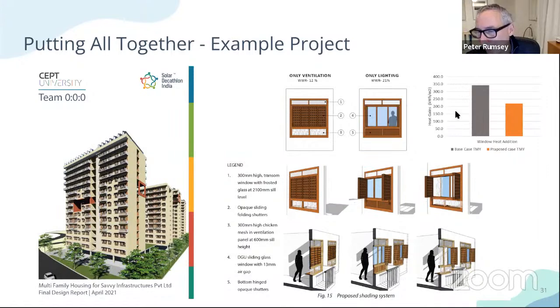So at the end of the day, compared to the base case building without the shading, the heat gain from the building envelope - that's our load - was about 350 kilowatt hours per square meter. Their better design came in below 250. So in essence they got something like a 35% reduction in the cooling requirement at the facade.